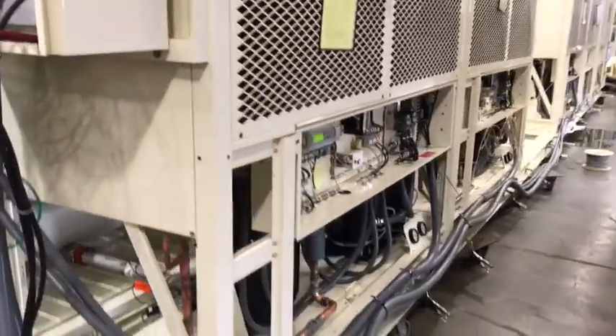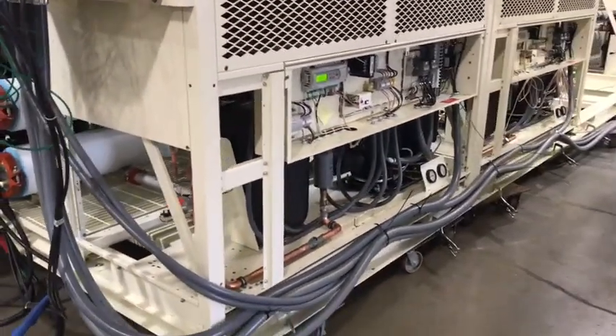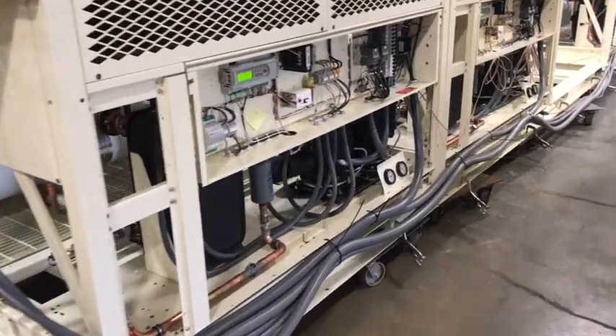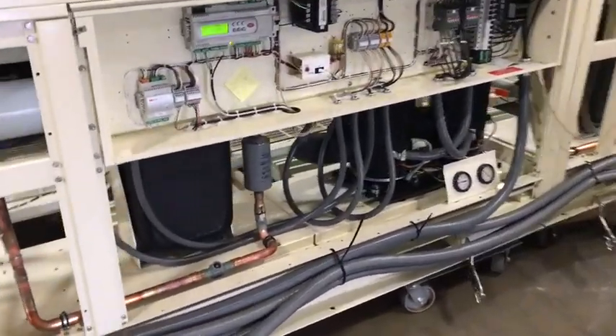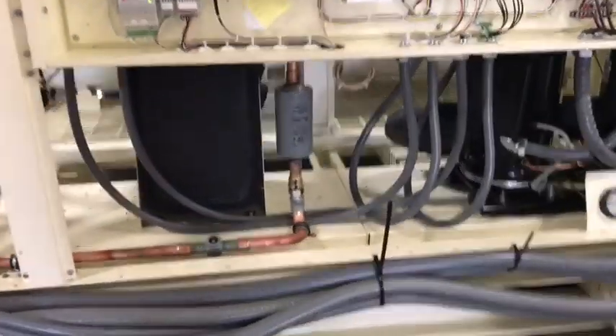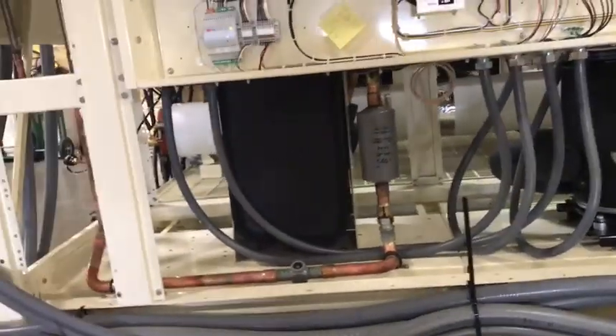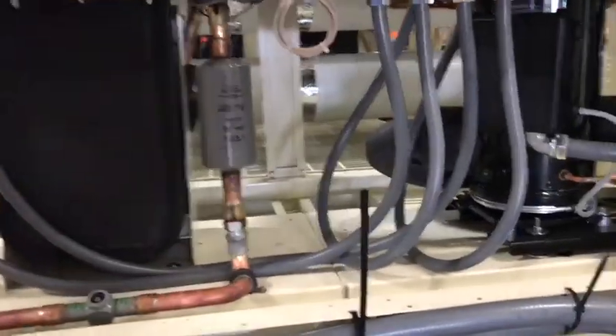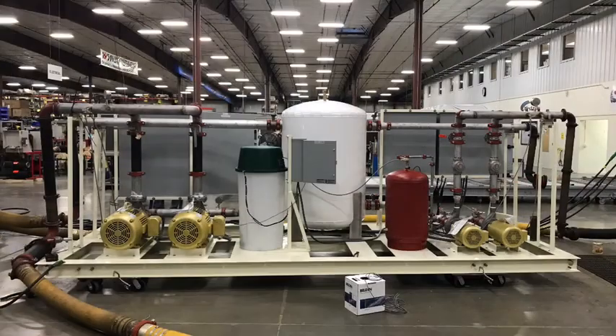Now looking down the back of the array, we can see 2 additional slave modules. We'll get a close-up view of the lower half, working from left to right, the brazed plate evaporator, filter dryer, and then the tandem compressors.